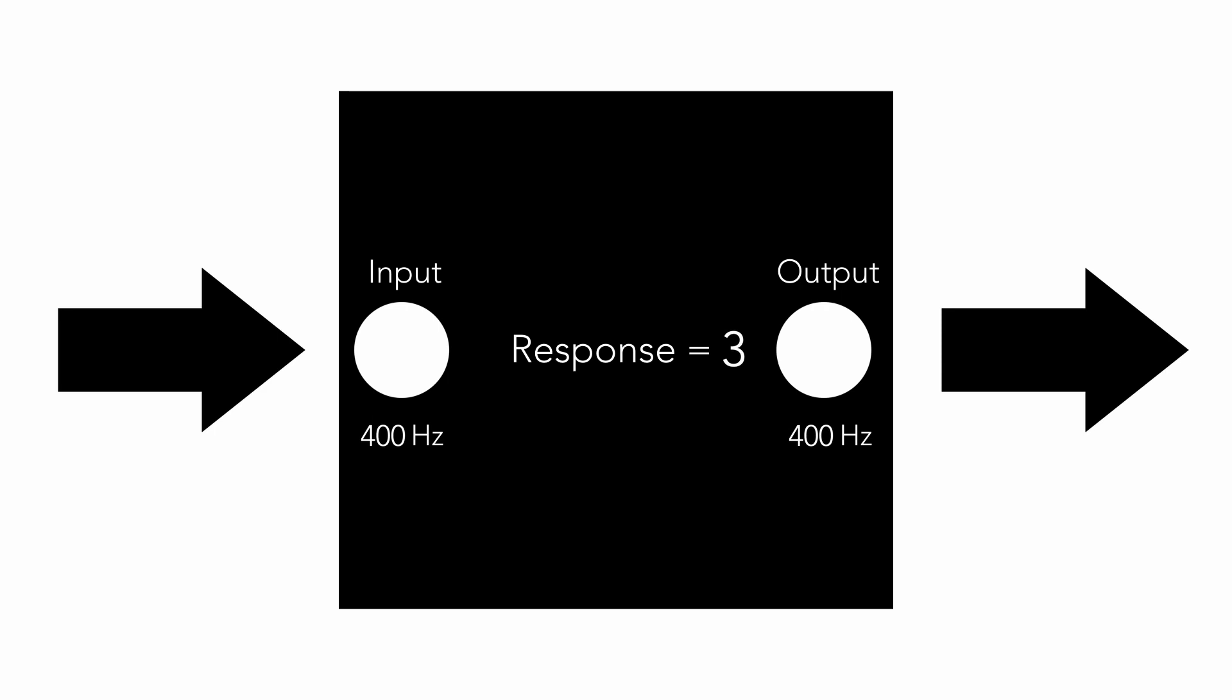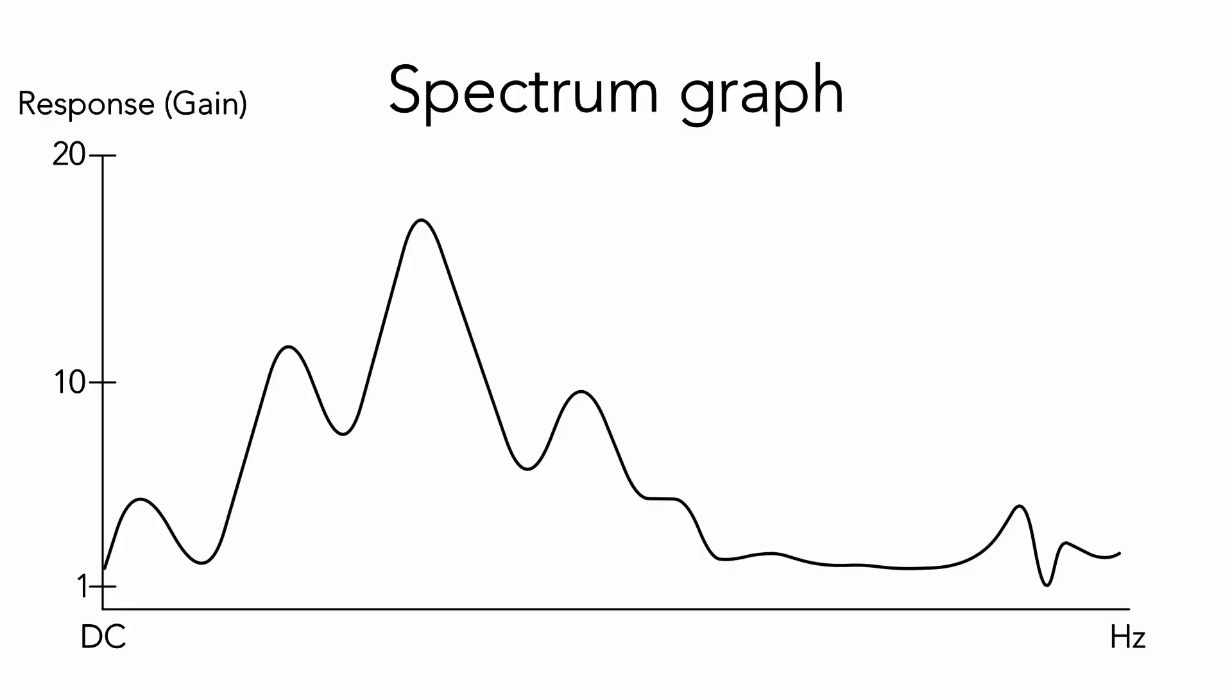We measured all response gains. So we get 1 DC gain and 400 lines of AC gains from 1 to 400 Hz. It looks like spectrum with 401 lines. That is true. It is very similar. And actually that is the frequency response function.